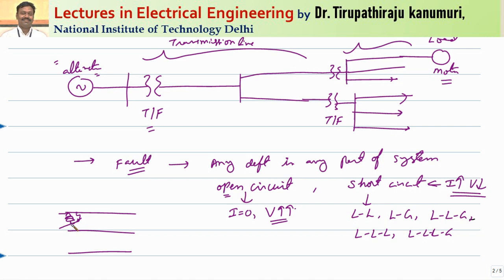These flashovers can happen because of switching transients or lightning strokes, during which voltages increase drastically. Similarly, some bird, animal, or object — for example, during wind or rainy season, a plant branch — may come and fall on the transmission line. The plant can fall between two conductors or may touch all three conductors, and accordingly it will be converted to the equivalent fault type.